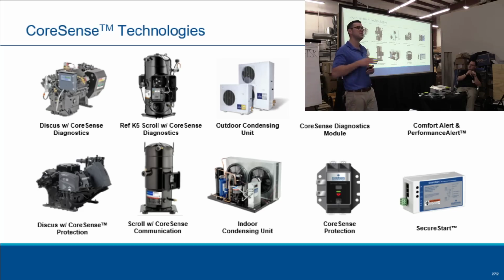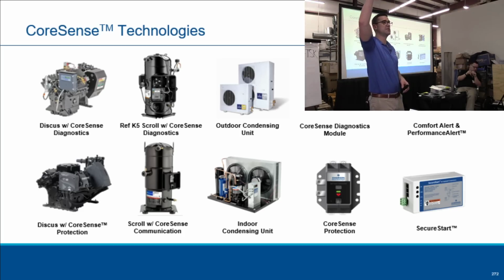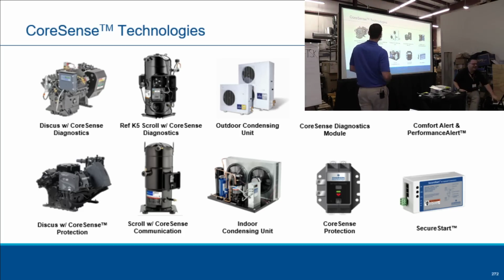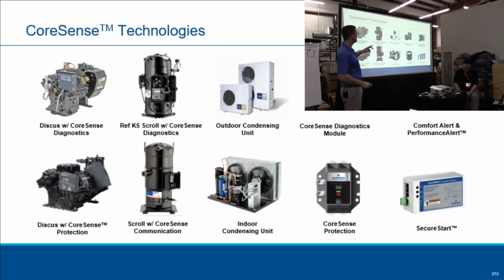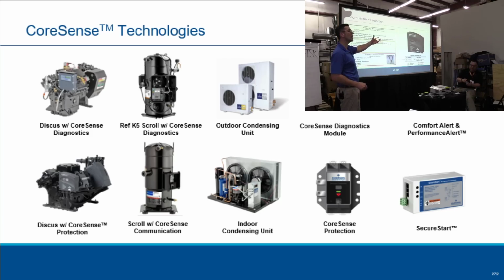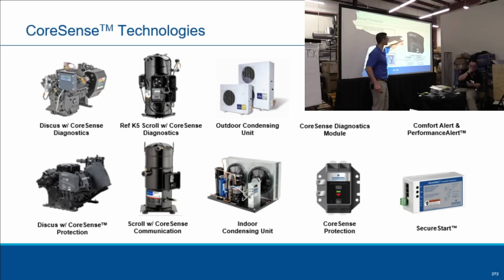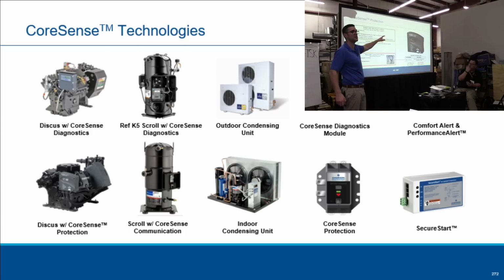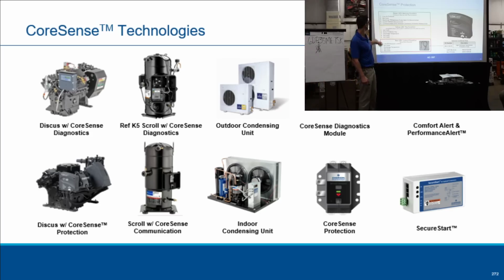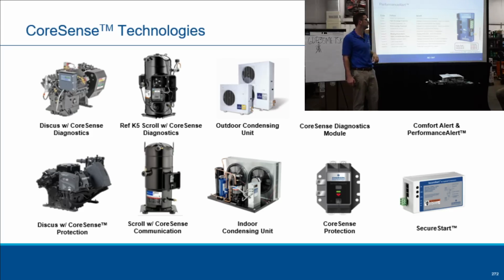Okay. So CoreSense, how many people have heard of CoreSense? Show of hands. 1, 2, 3, 4. Awesome. Okay, we have many different CoreSense modules, but the ones I'm going to focus on today are for our Discus compressors and our air conditioning compressors. This is our CoreSense module. The way it works, if you get an alert, like low oil pressure, all of a sudden you've got a flashing light. Do you think a flashing green light is good, or something you should look into? You've got to look into it. Low oil pressure, right? It's flashing. If it's on solid, it's good. But if it's flashing, you have an issue.